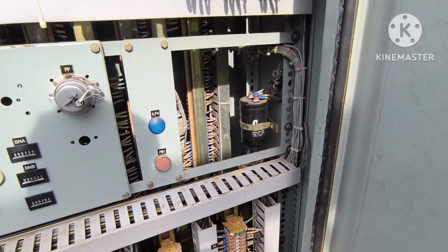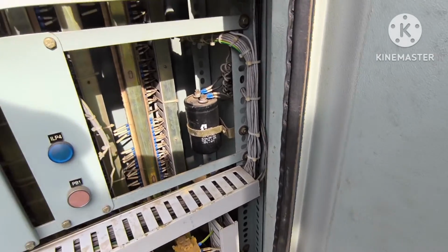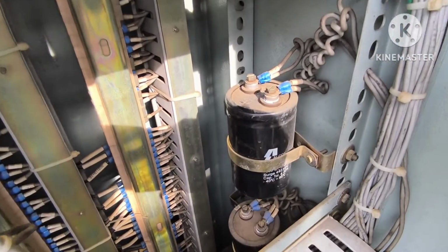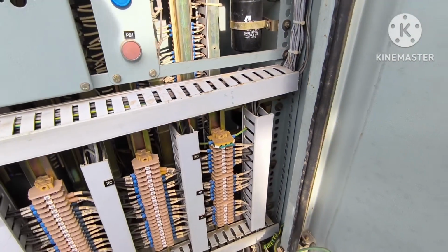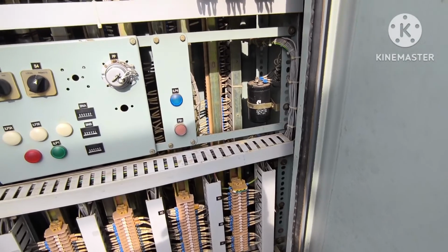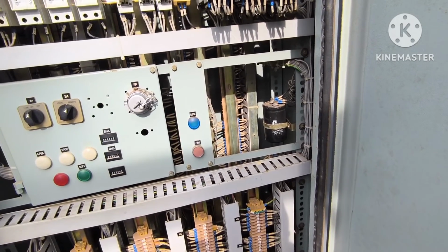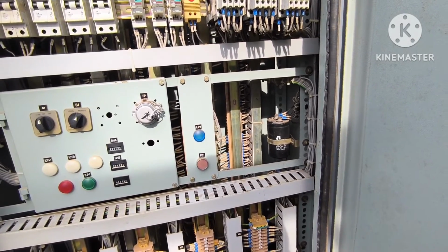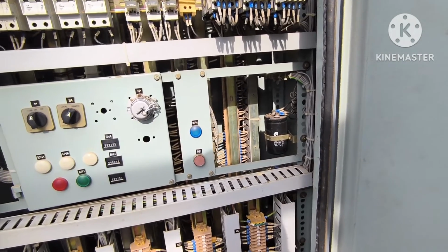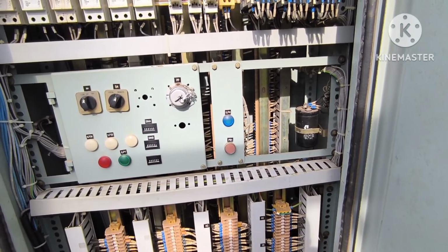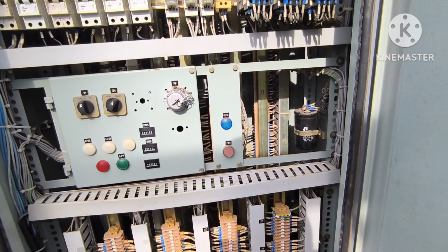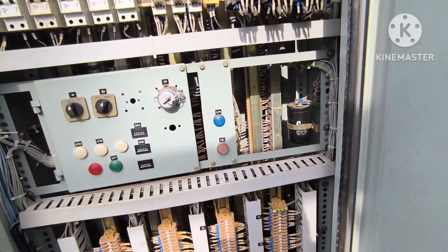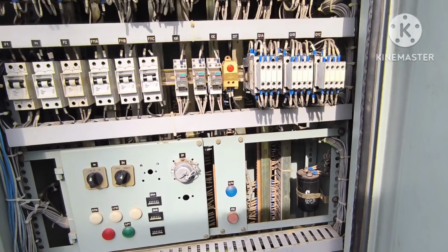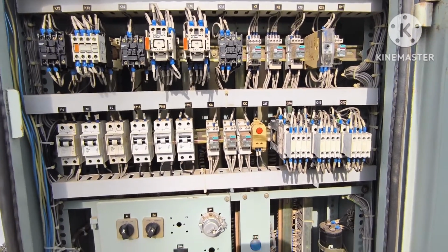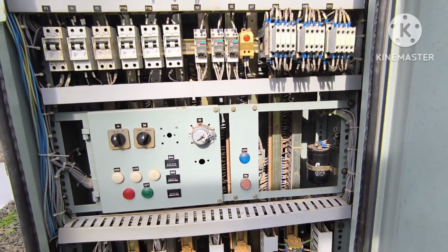Apart from this there will be 3 capacitors. You can see here, these 3 capacitors. This is called the DC fail capacitor strip. We are utilizing 220 volt DC here. So due to some reason, if there is a failure of DC supply, the breaker will trip immediately. This is the function of that capacitor strip.